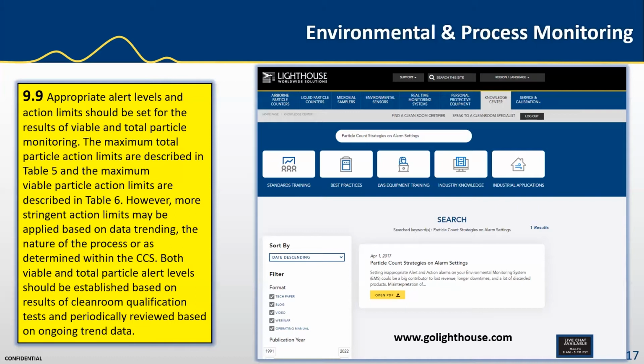one-off event. That's 1 minute, and you could have 4 hours of zero counting, one event that will trigger an alarm, and then 4 hours of zero counting again. What's the probability of that being a biological event, an excursion that can have a detrimental impact on the product? What's the probability of that one event getting into those little vials and the diameter of the vial? So you've got to think about the whole thing from a holistic approach. And I really do encourage setting your particle count strategies on alarm settings based on trending and X out of Y events. And that paper that I've discussed here on our website will definitely give you some good insight.